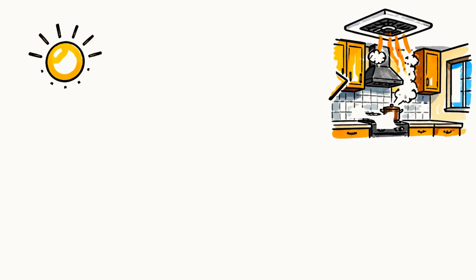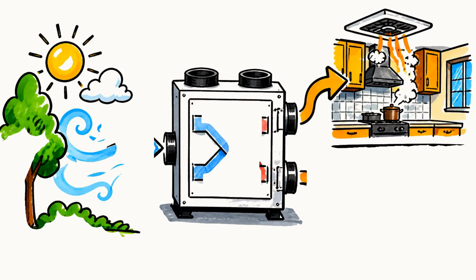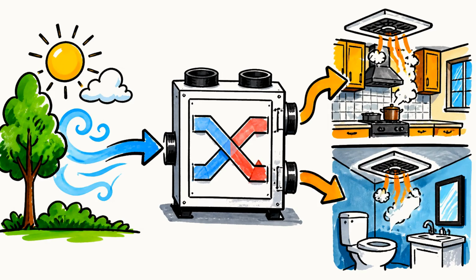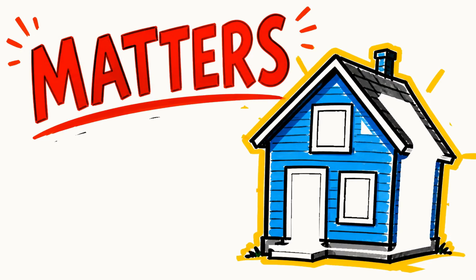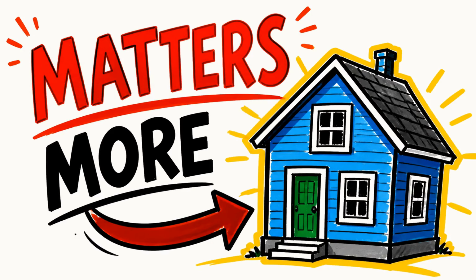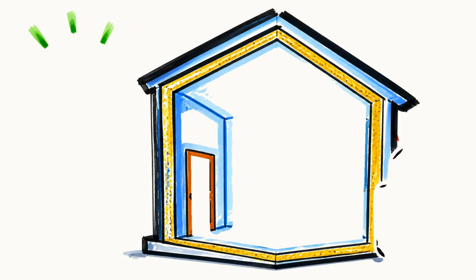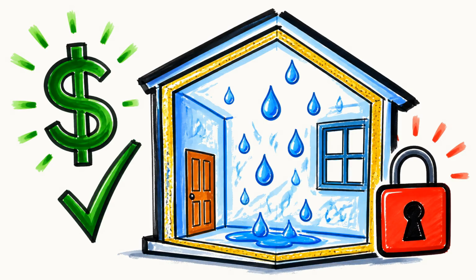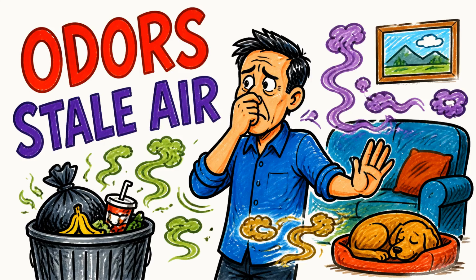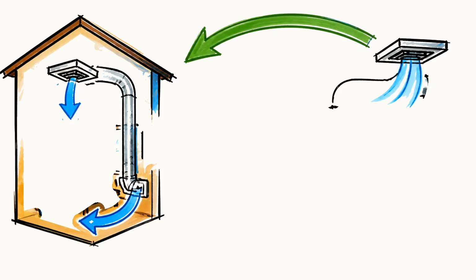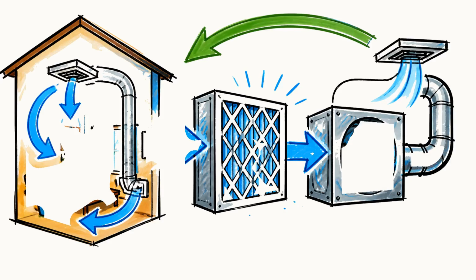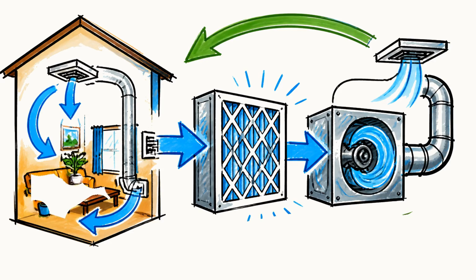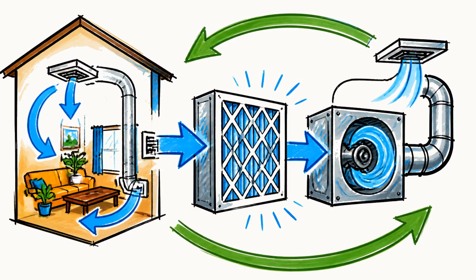True outdoor air ventilation is a separate add-on, things like an energy recovery ventilator or the exhaust fans in your bathroom and kitchen. And it matters more than it used to, because newer homes are built tighter to save energy, which is great for the bill but traps humidity, odors, and stale air inside. So for most houses, the HVAC is really filtering and moving air, not swapping it with the outdoors, unless somebody added a system built to do exactly that.